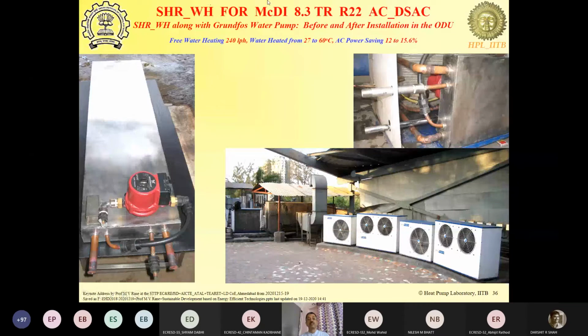Then these were the superheat recovery water heaters for McDI, where 240 liters of water was heated. Okay, and the power consumption reduced by 12 to 15.6% compared to the one without the desuperheater. Okay, in this case, the desuperheater was packed within the condensing unit itself. These were the older condensing units where we had enough room inside.